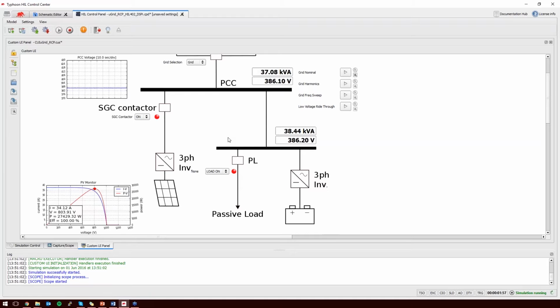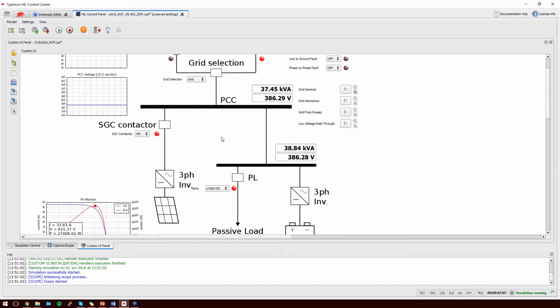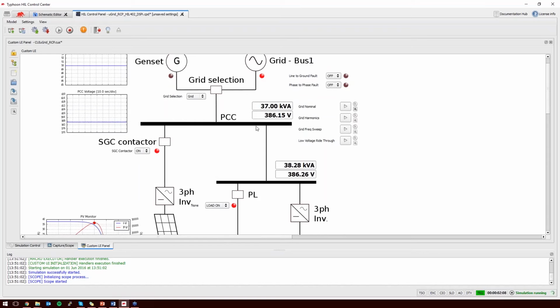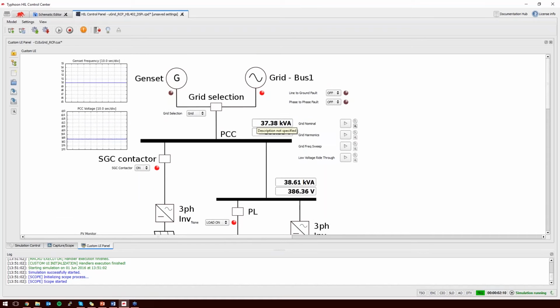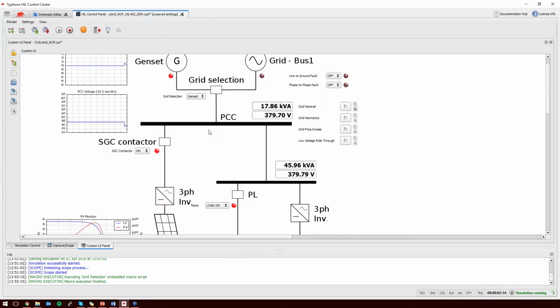The key point is to verify all your testing with hardware-in-the-loop in real time, make those adjustments and fixes, or rerun those scenarios inside the offline simulation, tune things up again, and then bring it back, generate more code, and bring it back to the HIL simulation.